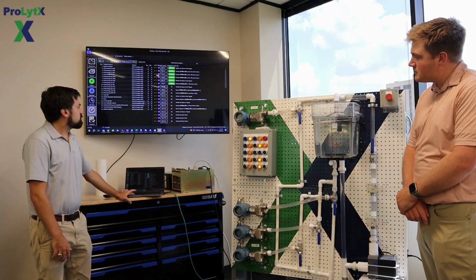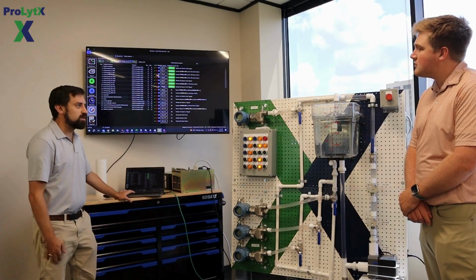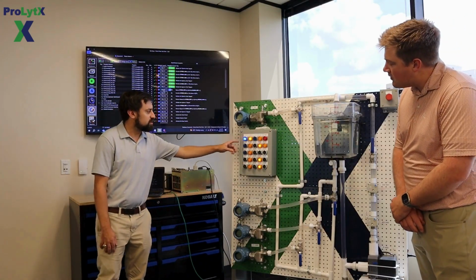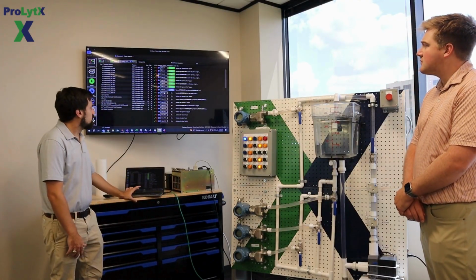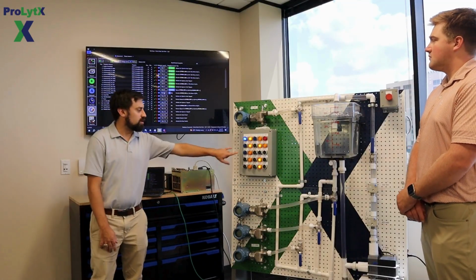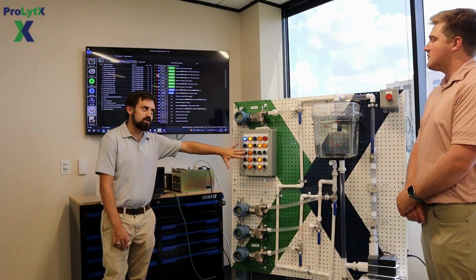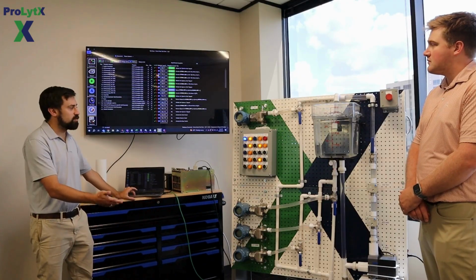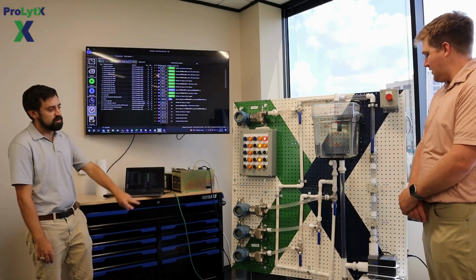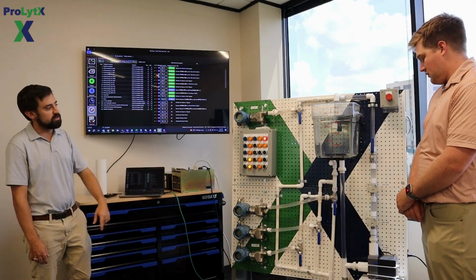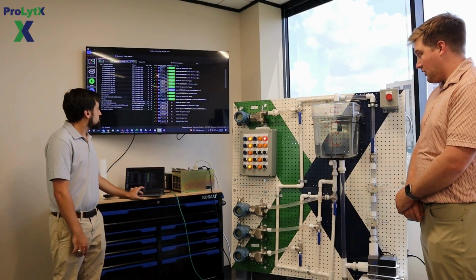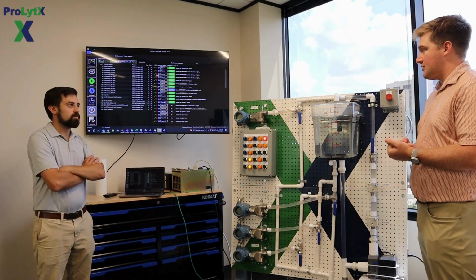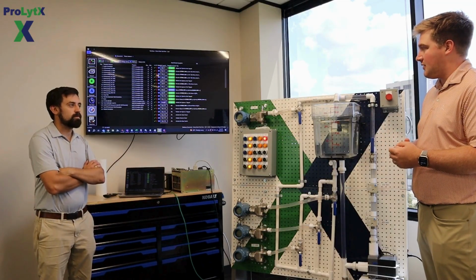Now that we simulated that 1 is tripped, we're going to confirm we're still not tripped, 2-out-of-3 voting. So we're going to hit the bypass next on A. The bypass comes on, so we're essentially not tripped at all right now. And we'll go ahead and trip B. So now we have 1 tripped, and another trip. This one's bypassed, so we're still not tripped. As soon as I confirm that we're not tripped again, I remove the bypass, and we should trip. Yep, there we go. Both valves closed, motor stopped, trip light came on. Okay, so we successfully drove a 2-out-of-3 analog and a 1-out-of-1 discrete trip for this demo panel. Great.